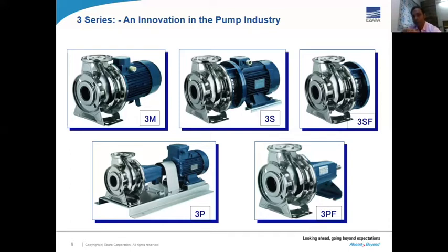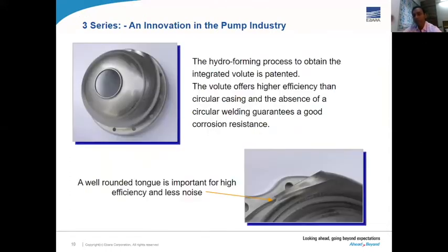The volute casing is manufactured by a hydroforming process, which I'll show you a picture of later. This is one product we are really pushing into India, where you have a pressure requirement of 6 bar or 7 bar; this product is really feasible. It's an efficient product, it's economical as well, and it has low maintenance. So this is how the casing looks.